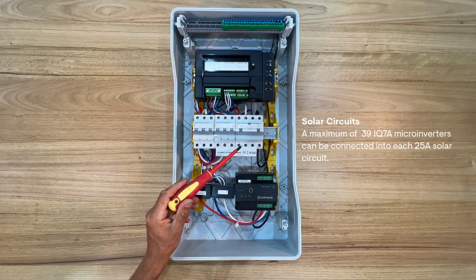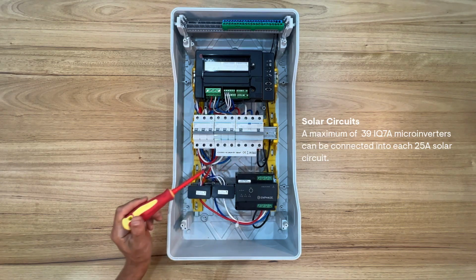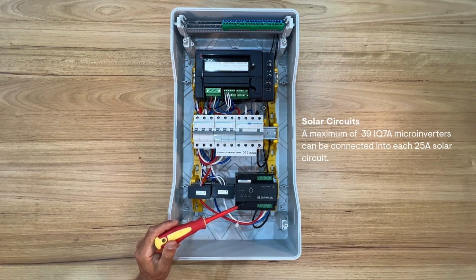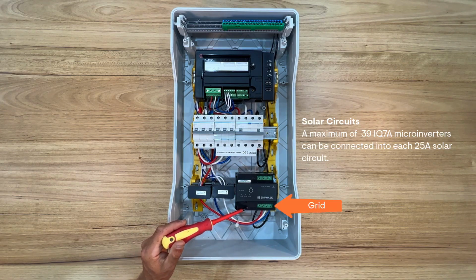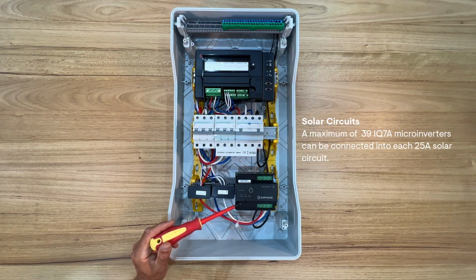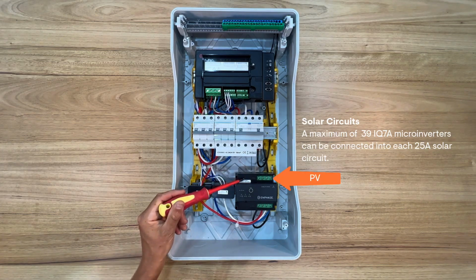Each phase of the circuit is wired through to the multi-phase Q relay and connected to the grid terminals labelled on the Q relay. The Q relay is wired in series in line on each microinverter circuit. Now you may have one or a number of Q relays depending on the number of microinverters installed. Each phase of the solar AC circuit is wired into the PV terminal side.